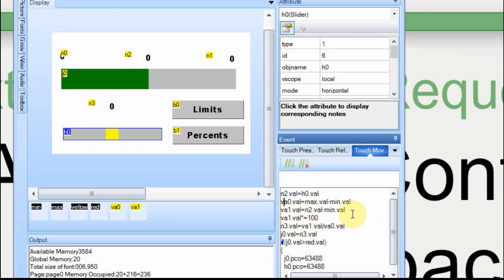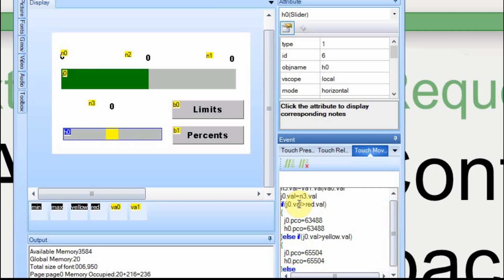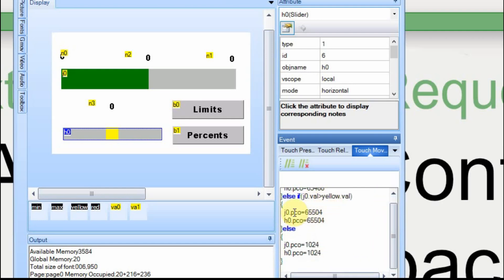I take the value of N2, subtract it from the minimum, multiply by 100, then divide by the total range — that gives me my percentage. I store that value in N3. Then I set J0, which is my progress bar, equal to that value so the number in N3 is the same as the progress bar. Based on the value of the progress bar, if it's greater than red I make it red, if it's greater than yellow I make it yellow. If it's less than red it goes to the next check; if it's less than yellow, it falls through to green. And that's how this portion works.